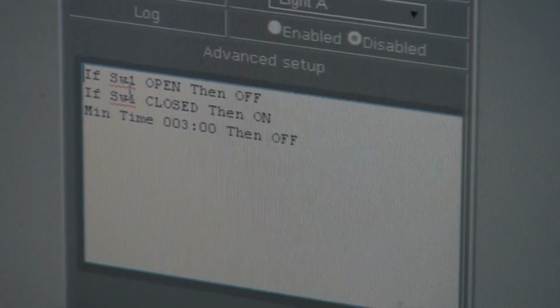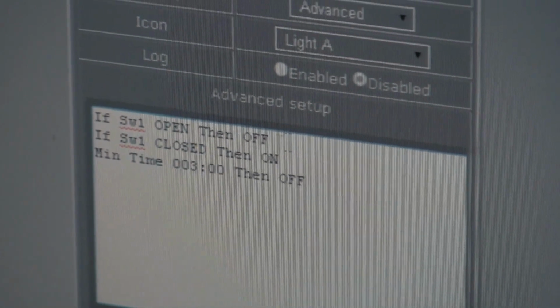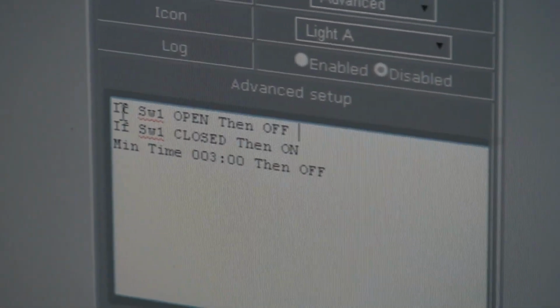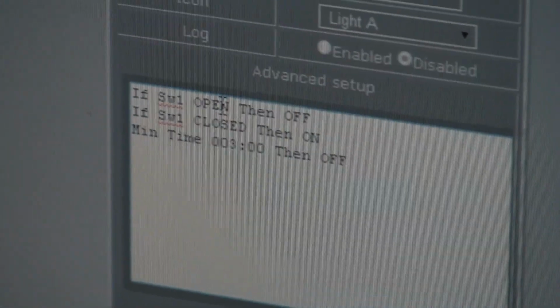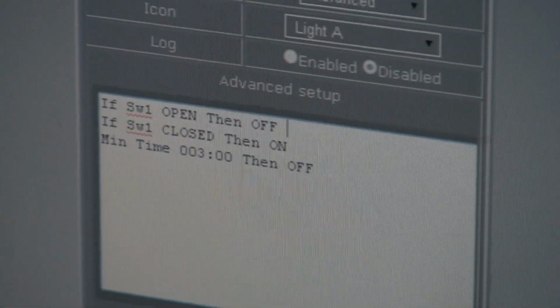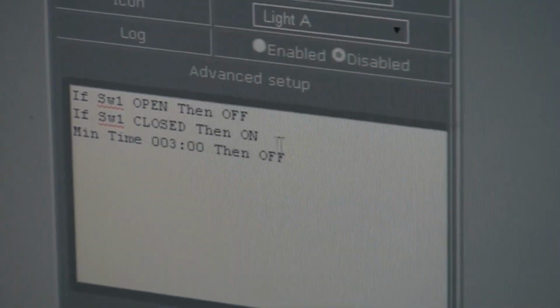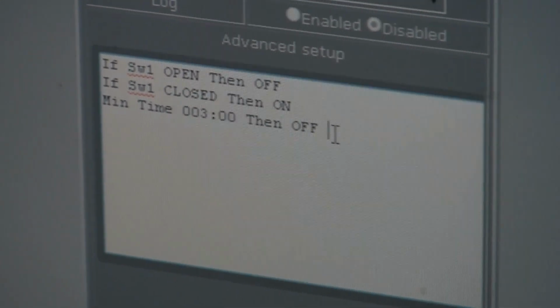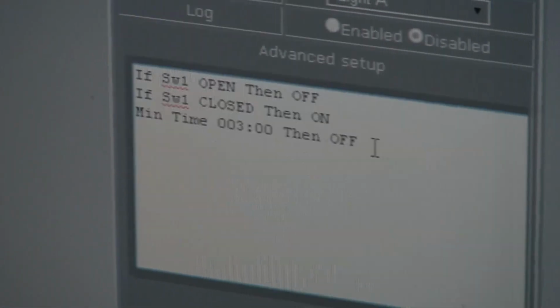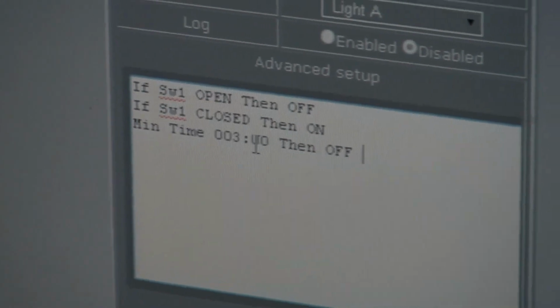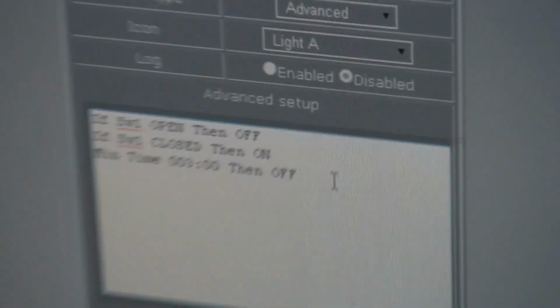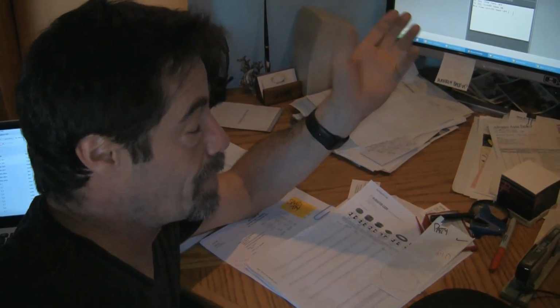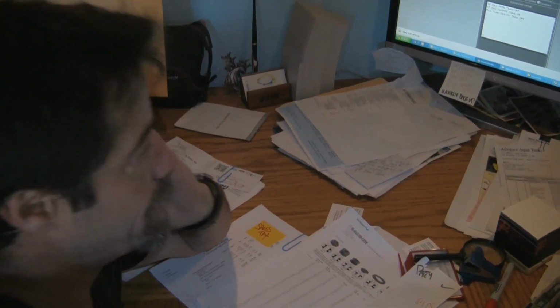Switch 1 in his case is our ATO float switch. So this is saying if switch 1 is open, then the ATO pump — or in this case, Add Water — will be off. If switch 1 is closed, it'll turn on. Min time here means the float switch has to remain in that state for a minimum of 3 minutes before it'll turn on. So min time 003:00 means that if there's water bouncing around in the sump and the float switch bobbles, we don't want the pump turning on and off repeatedly because of that. It has to remain in a specific state for 3 minutes before the pump turns on. It's a little counterintuitive — min time 3 minutes, then off — but that's just how it works.